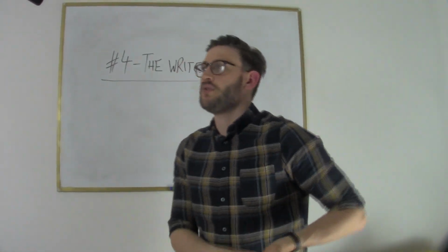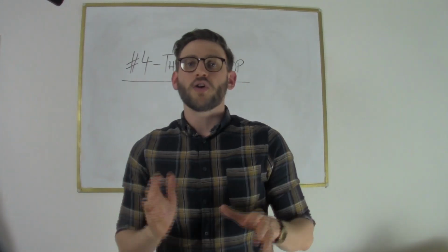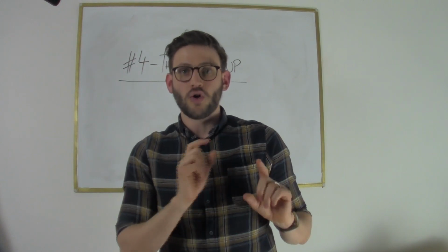However, if I went to door number 1 in the lounge and that was poor, and then I went to door number 2 and that was crap, and then I went to door number 7 and that was rubbish, and door number 12 and that was rubbish, then door number 20 was rubbish, and then I come across another door and that was crap, and went to the plant room and that was crap, I'll be like, okay, now we've got a significant problem here. You are obviously not maintaining your fire doors. That is a significant finding, and that goes into the significant findings section where it says, business does not have a maintenance scheme for their fire doors. So that's just one example of how we do it.